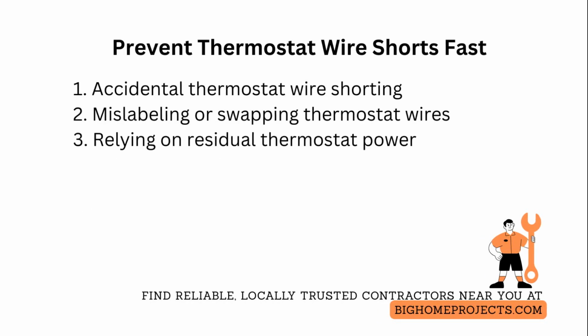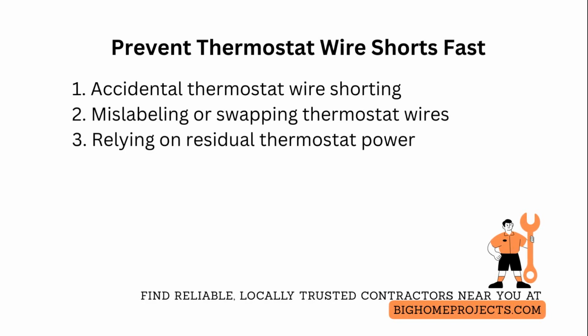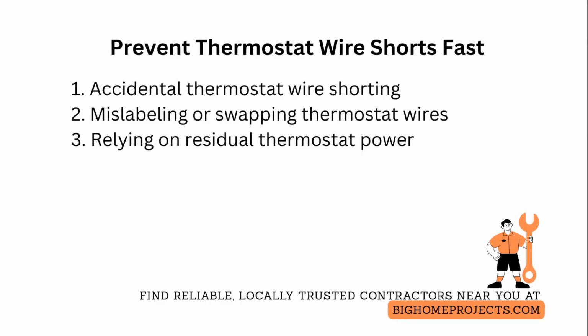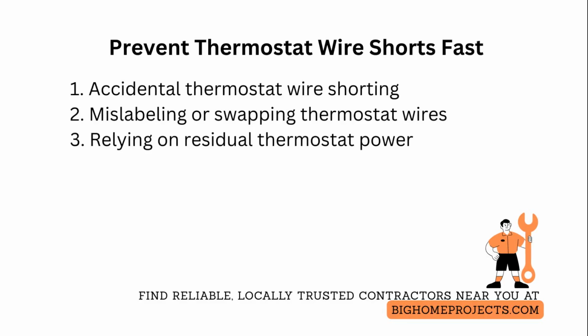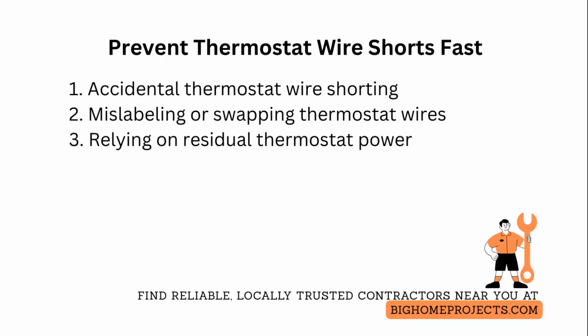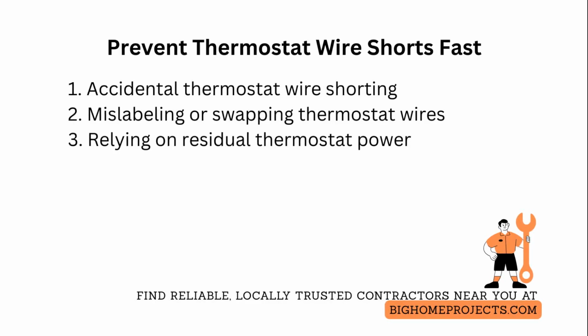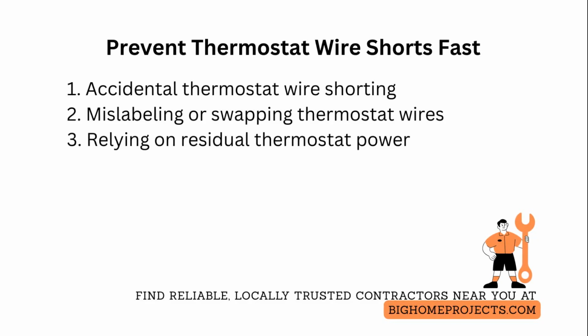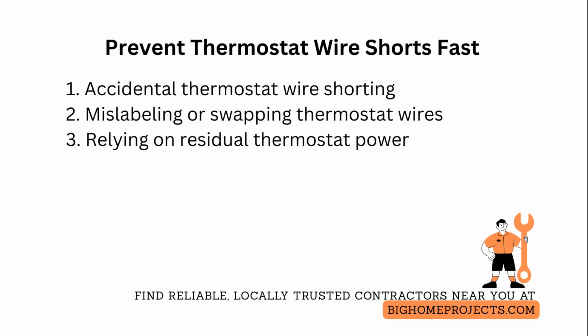One of the three most common mistakes is accidental shorting of thermostat wires, causing a blown fuse and no heat or cooling, which is fixed by powering down the HVAC at the breaker and replacing the fuse with the correct amp rating while verifying proper wiring labels. The second common issue is mislabeling or swapping wires that prevents proper equipment operation. Avoid this by taking a clear photo, labeling each conductor, and verifying terminal functions against the system schematic before reconnecting.